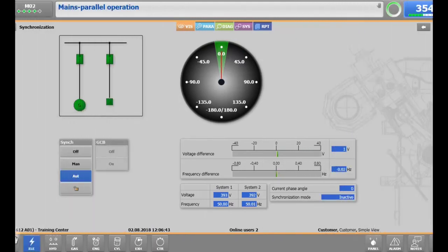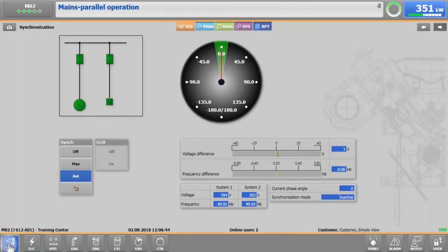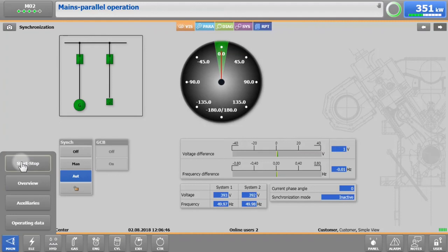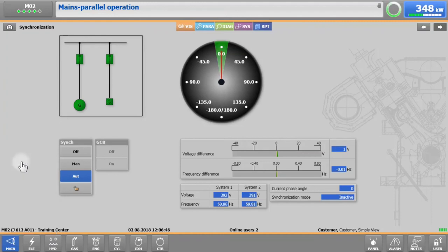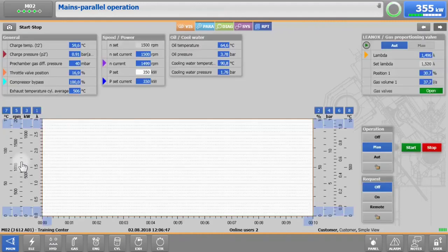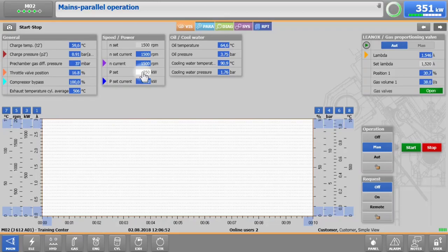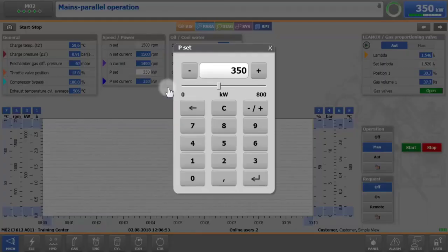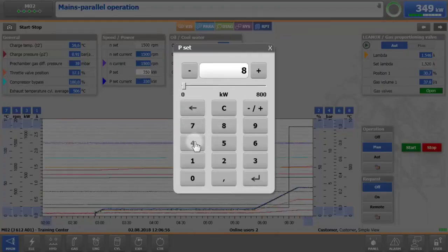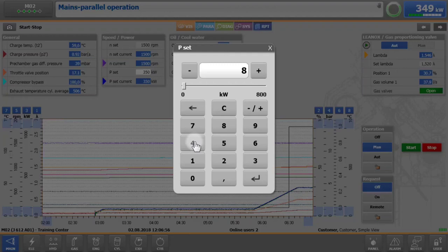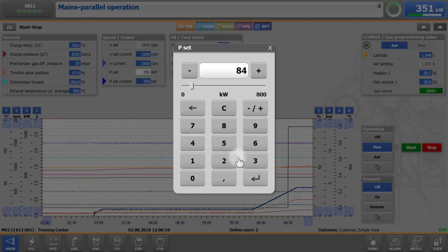To stop your engine in manual mode, go to main, start-stop and change the power setpoint to 10% of the nominal power output. In our case, this will be 84 kilowatts.